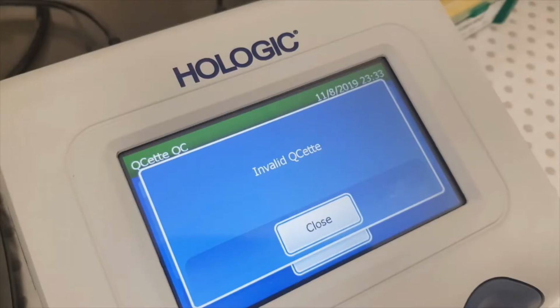If an invalid QCette message is displayed, restart the analyzer and confirm that the QCette serial number on the device and analyzer matches. This can be verified with the result printout. Also check that the QCette is clean and not damaged. If appropriate, canned air may be used to clean the device. If the QCette QC fails after a rerun, perform the QCette setup and follow the prompts. If the quality control procedure passes, no further troubleshooting is required.